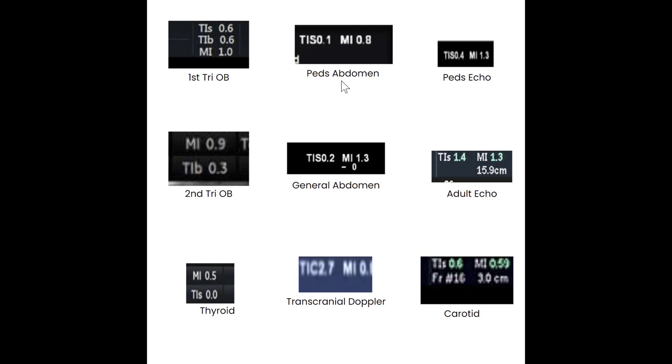Taking a closer look at PEDS abdomen and general abdomen, we are looking at soft tissue thermal indices. We have 0.1 and 0.2, very minimal. Looking at PEDS echo and adult echo, we see a 0.4 with PEDS echo and a 1.4 with adult echo. So we are actually potentially increasing temperature quite a bit with the adult echo settings.